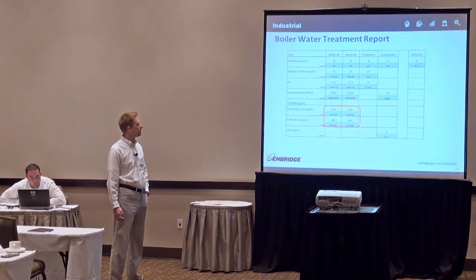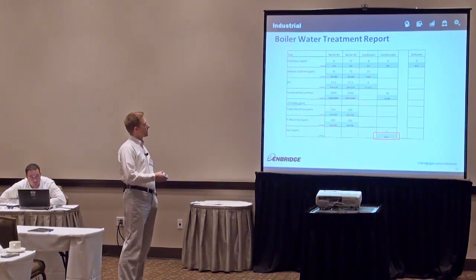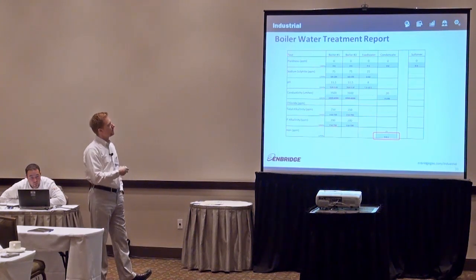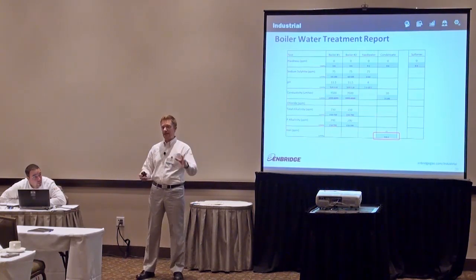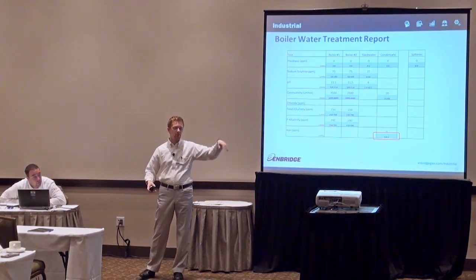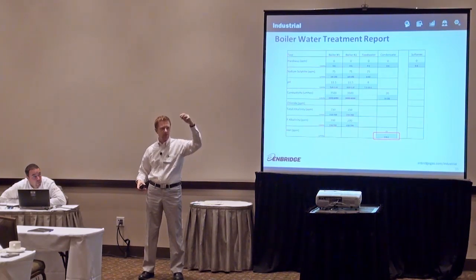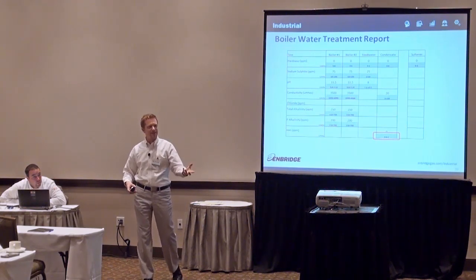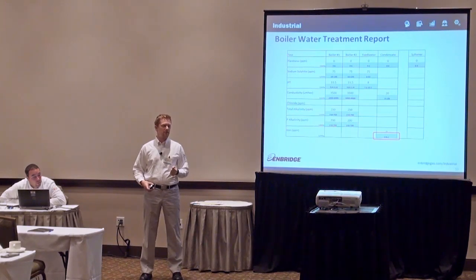to improve on that. Now, I did say we weren't going to get too much, or you said we weren't going to get too much into what's going on outside of the boiler room, but one thing to be aware of is I mentioned that when you produce steam from the boiler, any gases in that water also leave. Well, there is a reaction that happens inside of the boiler that produces carbon dioxide. Carbon dioxide travels with the steam. When the steam recondenses, when it gives off its latent heat into a process and turns back into water as condensate, the carbon dioxide dissolves into that condensate.